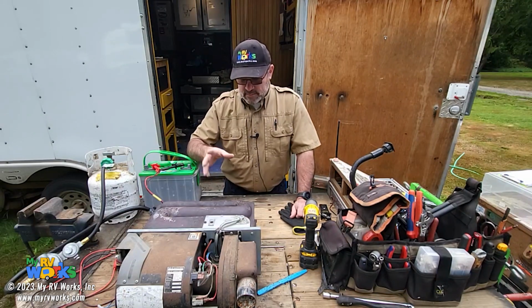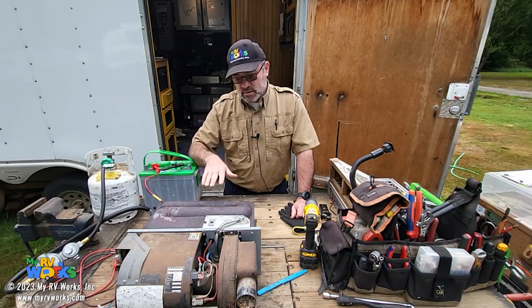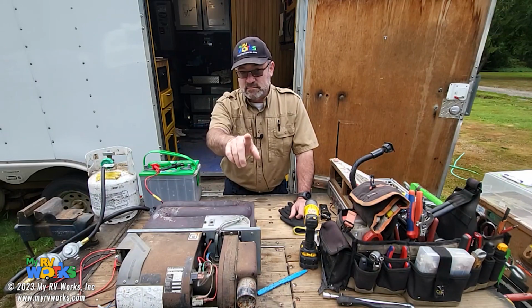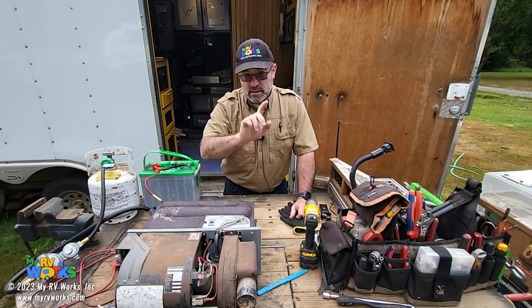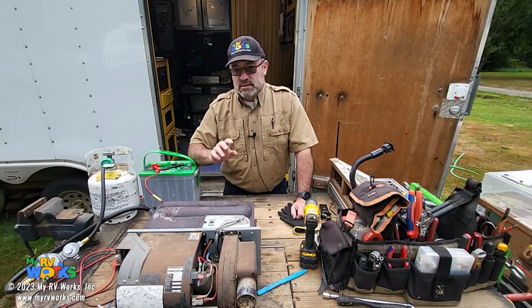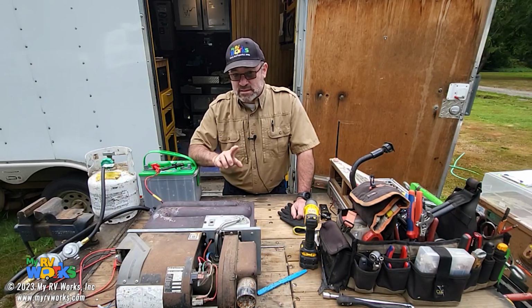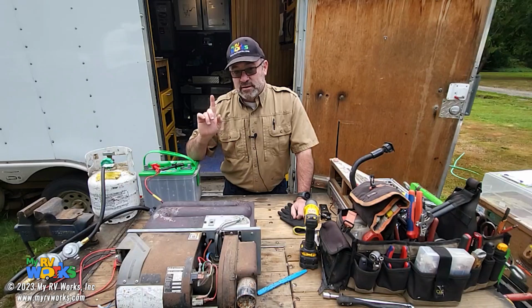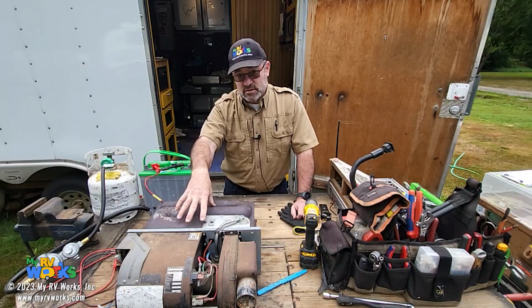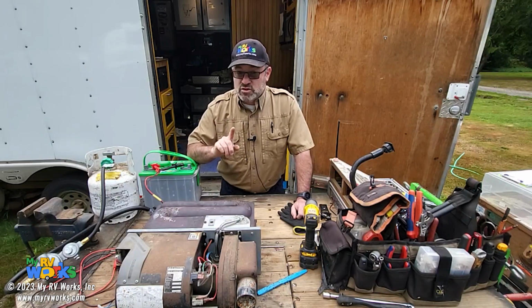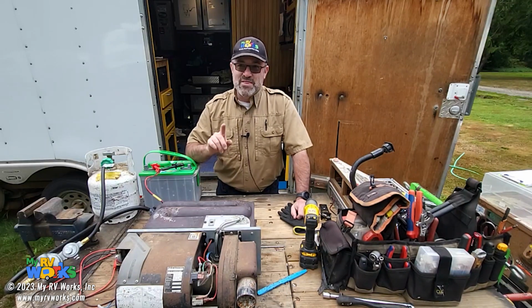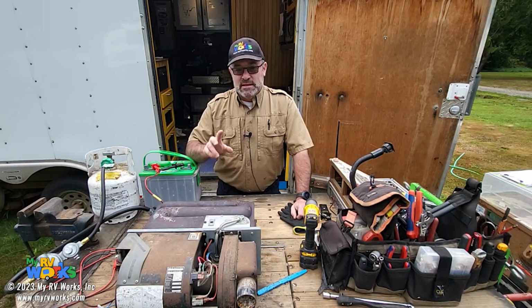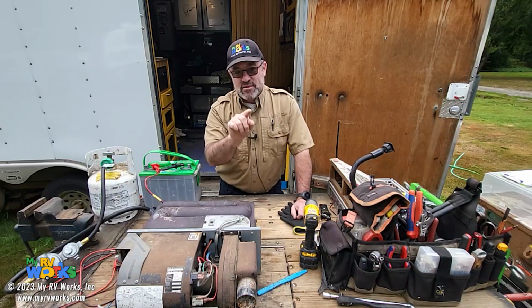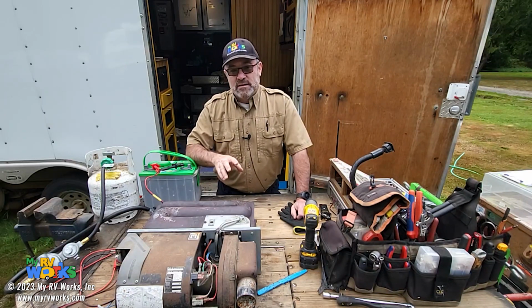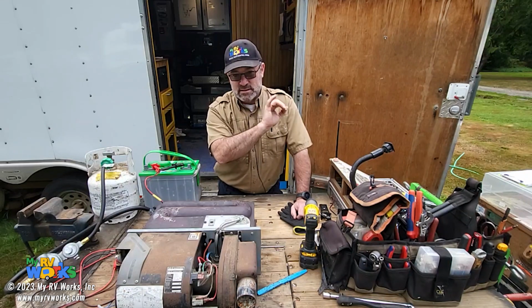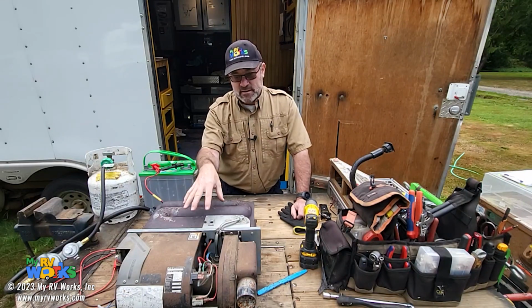Dometic furnaces, a lot of times their control is done up in the air conditioner plenum. More specifically, Dometic thermostat, Suburban thermostat. The Dometic thermostat is communicating to the air conditioner, which closes the wires that turn the furnace on. On a lot of your Suburban thermostats, boy, it's a mouthful, the control to turn the furnace on is done at the thermostat. Then you have the kind of thermostat that's just on a wall, and it's its own dedicated thermostat. So there's no blanket statement on how these things are wired.